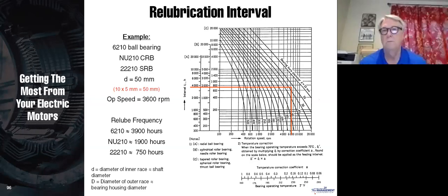How does a motor fail at high temperature? For example, if it is decided to bypass a temperature safety feature, for example, you have a bad RTD or whatever reason, what do you expect to see just before and just after a motor fails? Yeah, so we tend to talk about motor insulation, and that takes time. You don't have a high temperature and in 2 minutes the insulation fails. But if a motor is running at high temperatures, then you can see an insulation failure. It could be a turn-to-turn fault, or it could be a turn-to-ground fault. And you can generally measure those simply by measuring the motor to see if you have an insulation issue.